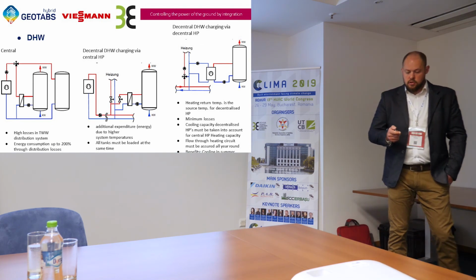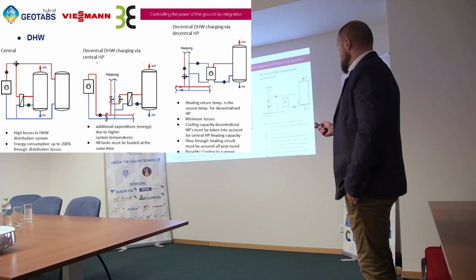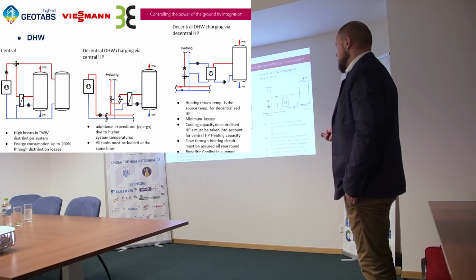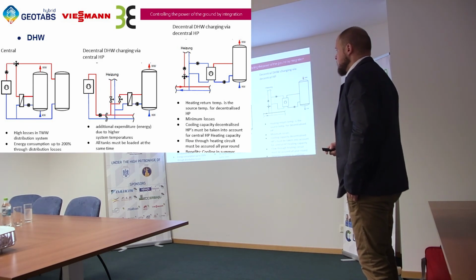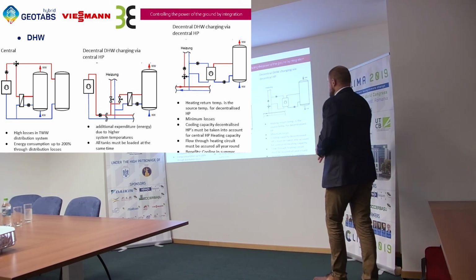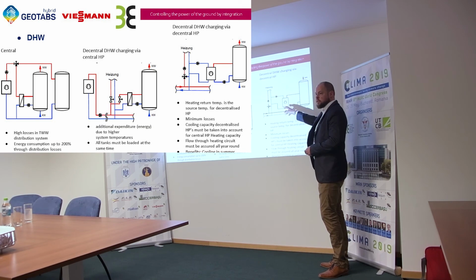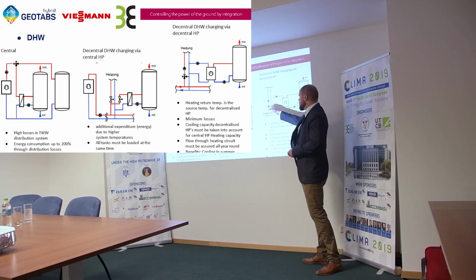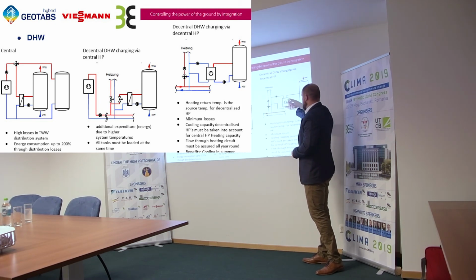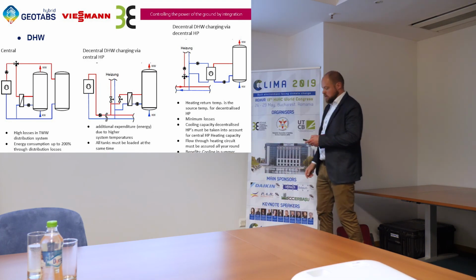Decentral can also be used, so if you have a building with a lot of apartments, you can send the temperature throughout the whole building for heating, and then when one buffer tank asks for domestic hot water, we have to increase the temperature. That automatically happens when the return temperature increases, the departing temperature increases, and we can load a boiler, a decentral boiler. What also exists are these types of heat pumps, booster heat pumps. They use the low source temperature here, 35 degrees for example, or the return temperature, and they can use this source to make a higher temperature to load a decentral boiler.